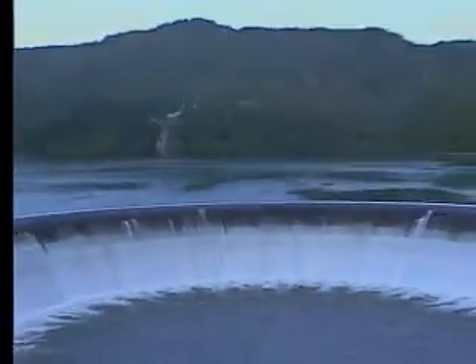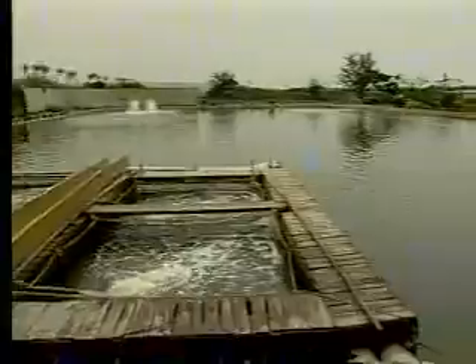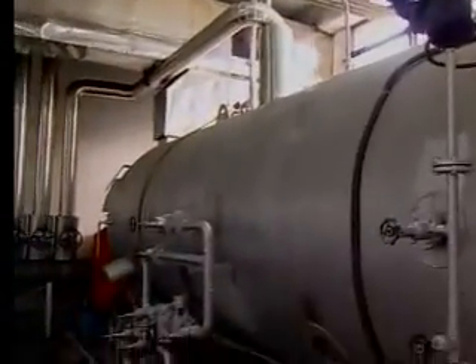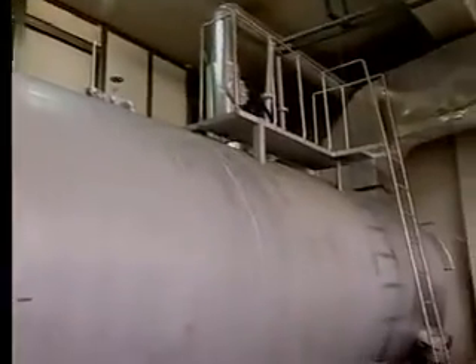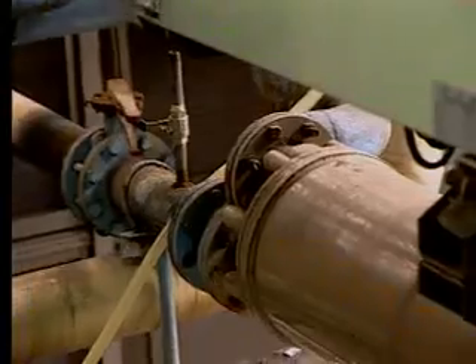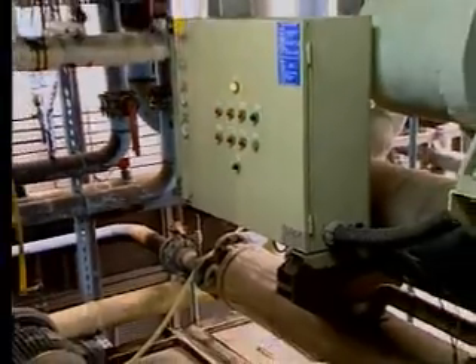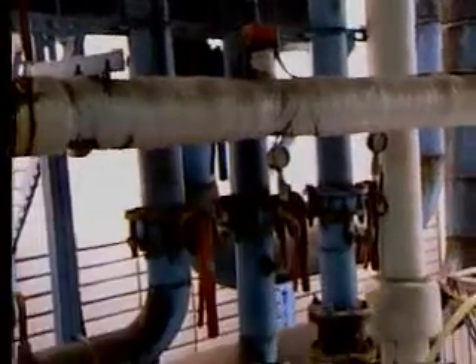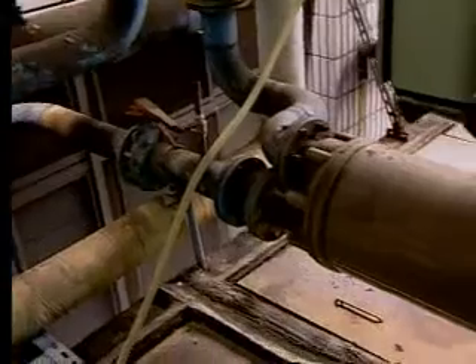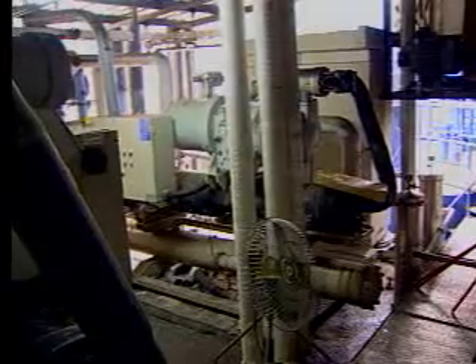Water, it's the only natural resource man cannot live without. For factories, whether converting water into steam to produce power or kill germs, or using it for cooling, diluting, or washing, water plays a critical role and is irreplaceable. However, when used in the operation of machinery, and when the internal temperature and concentration of the machinery rises and brings about changes in the particles floating in the water, scales and corrosion within the machinery result.